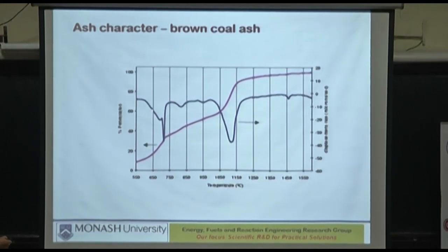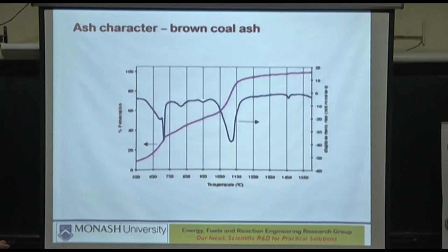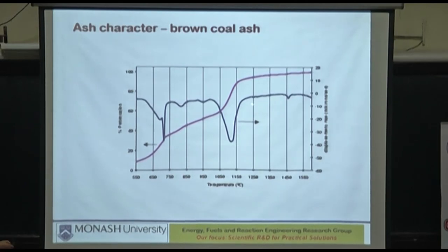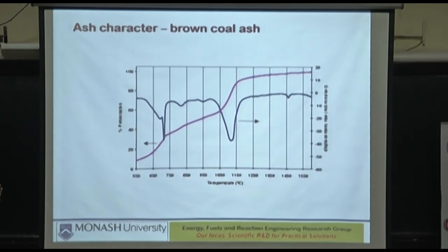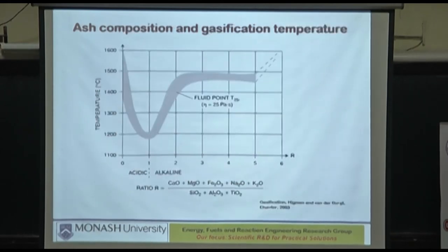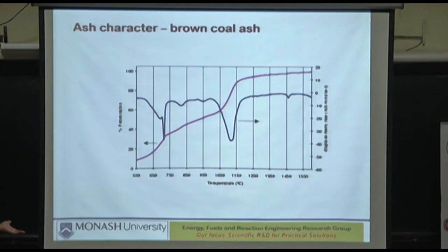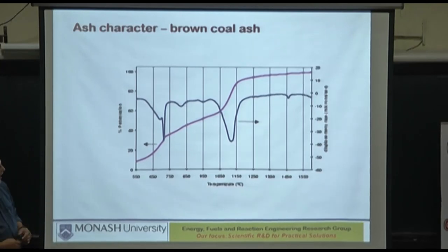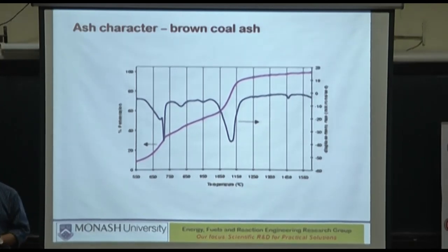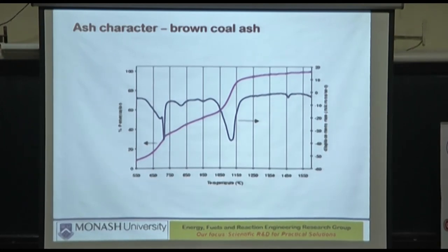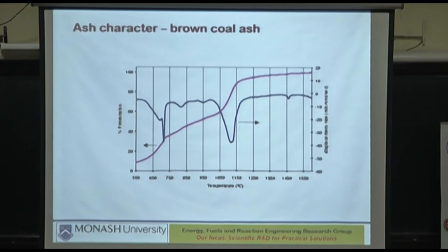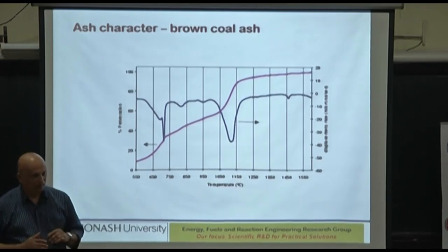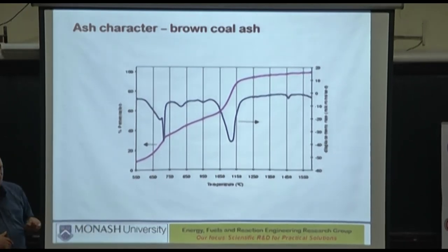So in this region, it is very unpredictable. Here comes a temperature zone that is somewhat predictable, and then here it is unpredictable, and beyond that it's all hunky-dory, no problem. Another one I haven't shown. There are lots and lots of these measurements, about 30 or 40 of them we did previously. And that's how we formed the decision: don't try to operate in a temperature zone which will be too narrow and too difficult to control, and therefore I'm ruling out pressurized fluidized bed completely.